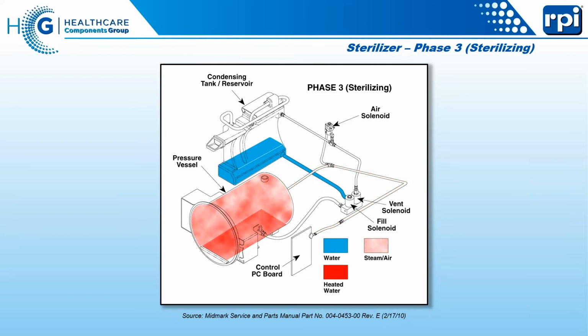But once we do reach the proper temperature and pressure, there is on the main control board a pressure transducer that keeps an eye to make sure that the machine stays at the proper temperature and proper pressure. There is also a temperature sensor mounted in the back wall of the chamber to measure the temperature as the machine is going on. So we're going to leave it right there for a minute till we can get the machine caught up to the talk.